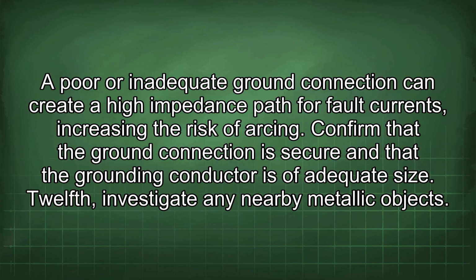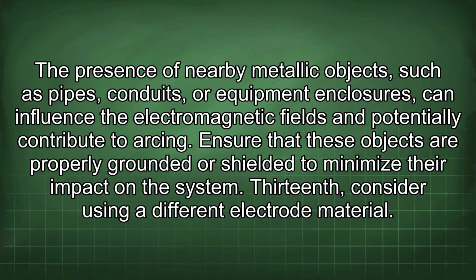12th, investigate any nearby metallic objects. The presence of nearby metallic objects such as pipes, conduits, or equipment enclosures can influence the electromagnetic fields and potentially contribute to arcing. Ensure that these objects are properly grounded or shielded to minimize their impact on the system.